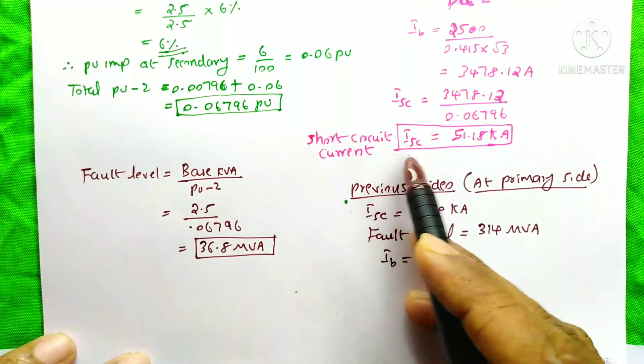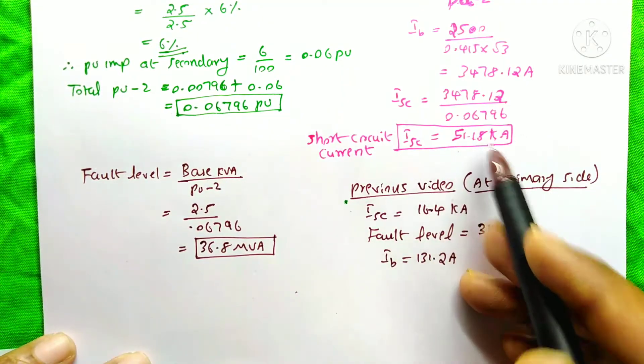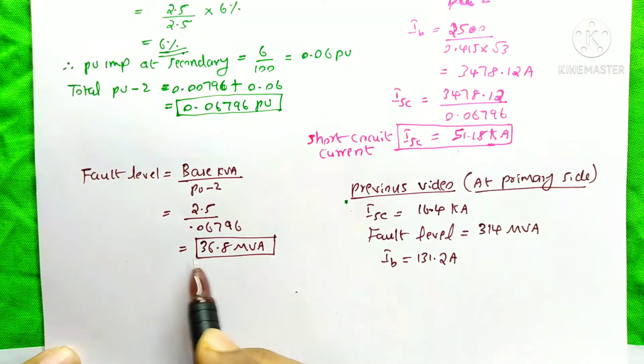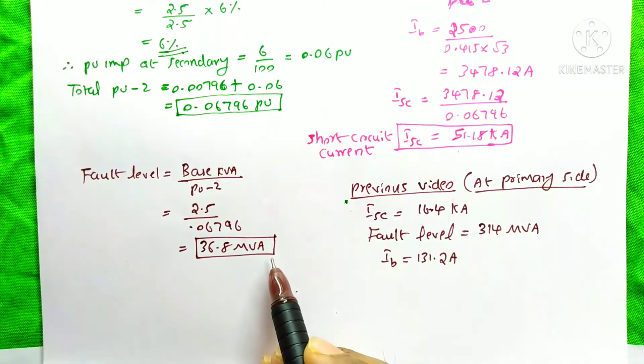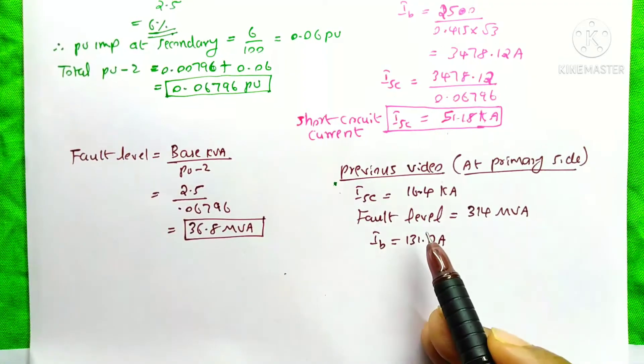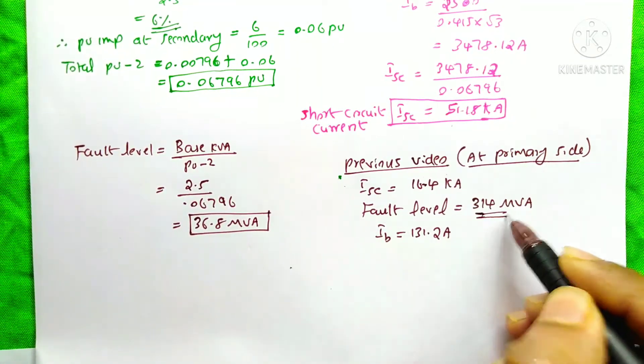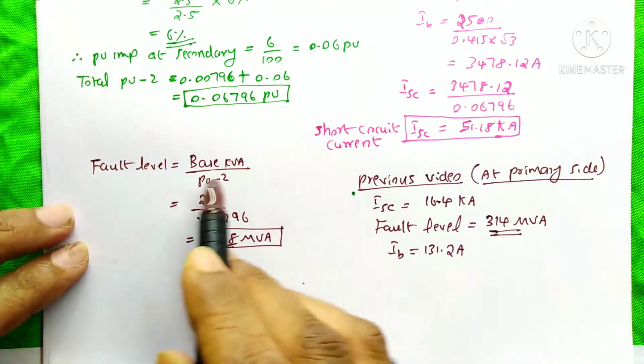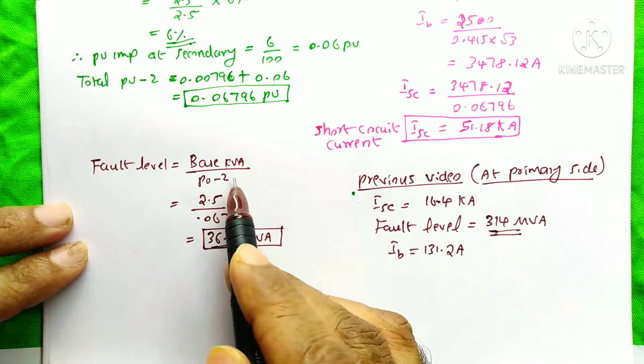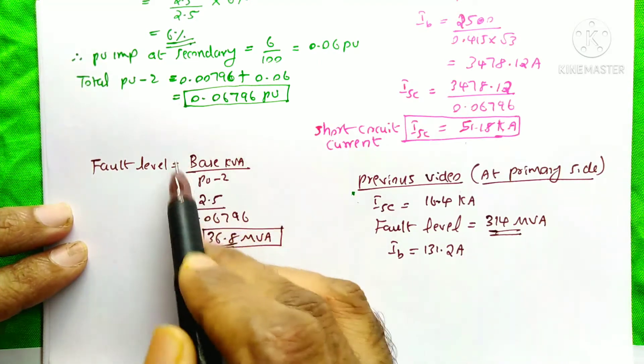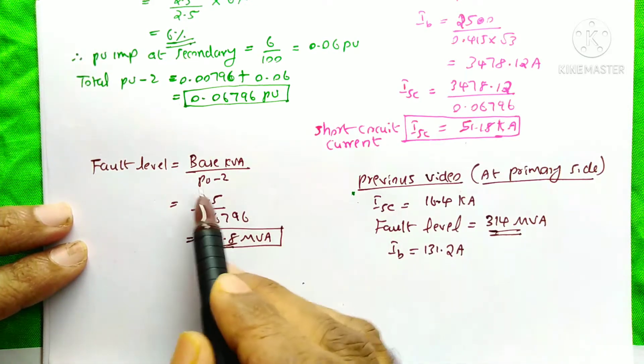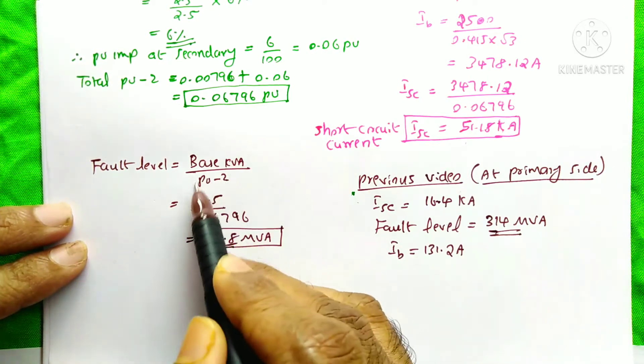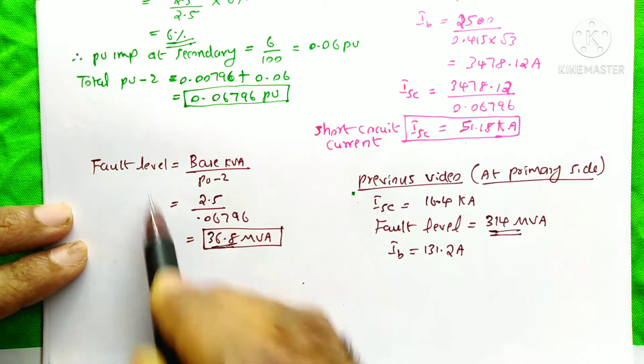When we compare the fault level: at the secondary side it is 36.8 MVA, but at the primary side it was 314 MVA — so the fault level decreased. The fault level equation is base kVA divided by per unit impedance. The base kVA is the same, 2.5 MVA, but the per unit impedance increased on the secondary. Whenever the per unit impedance increases, the fault level decreases.